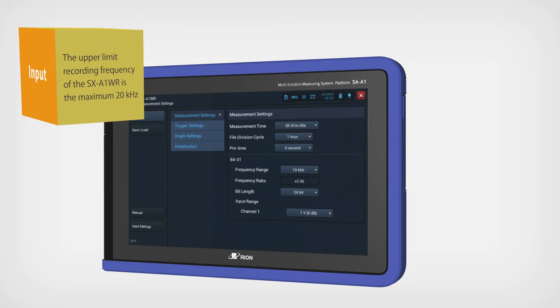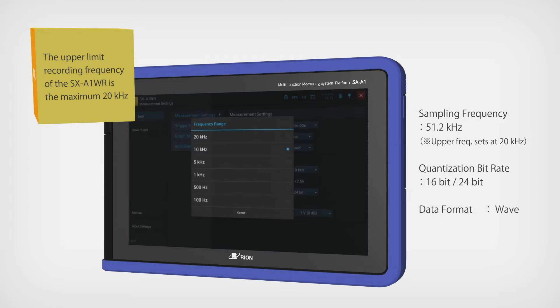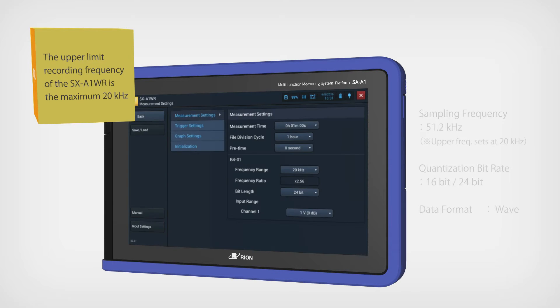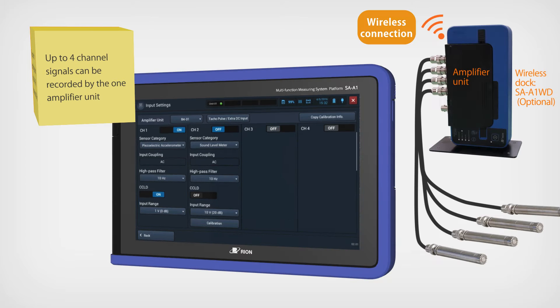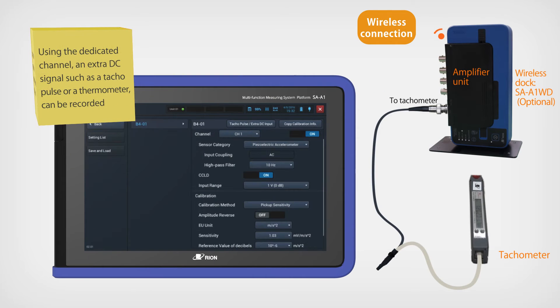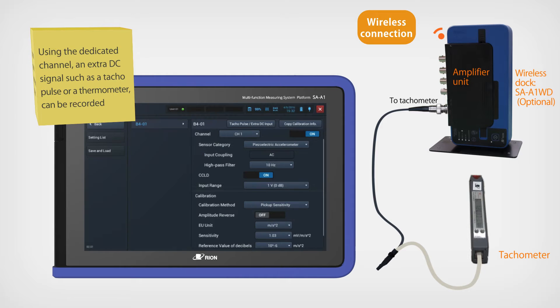The upper limit recording frequency of the SX-A1WR is a maximum of 20 kHz. Up to four channel signals can be recorded by one amplifier unit. Using the dedicated channel, an extra DC signal such as a tachopulse or a thermometer can be recorded.